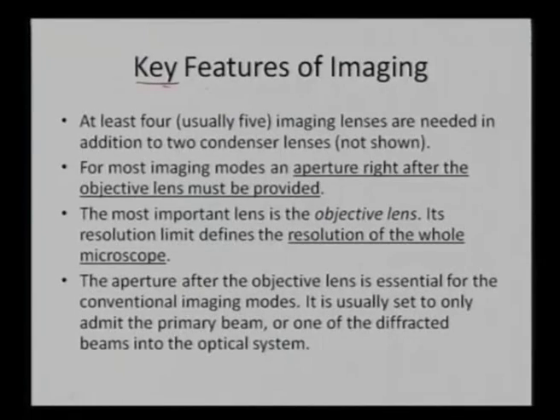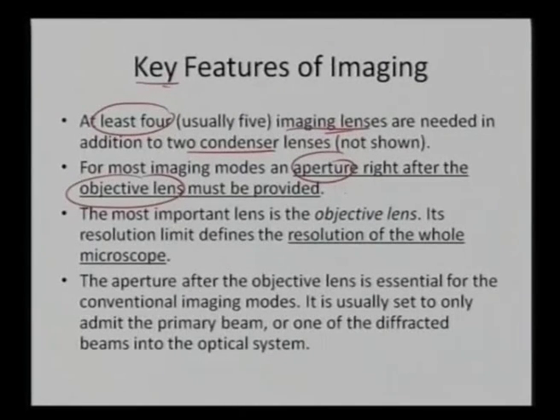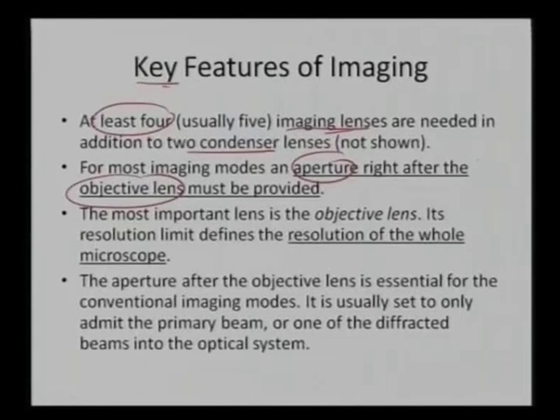There are certain key features required for imaging. We require at least three, four, or five imaging lenses in addition to two condenser lenses. For most imaging systems we keep an aperture just after the objective lens, because once we form the image plane and back focal plane we need that level to selectively choose whether to form a diffraction pattern or an image — and whether we want a bright field or a dark field image.